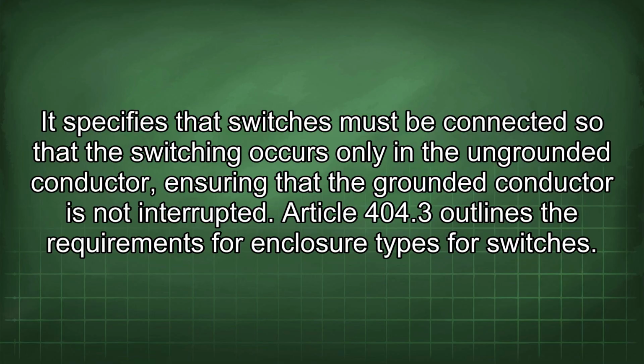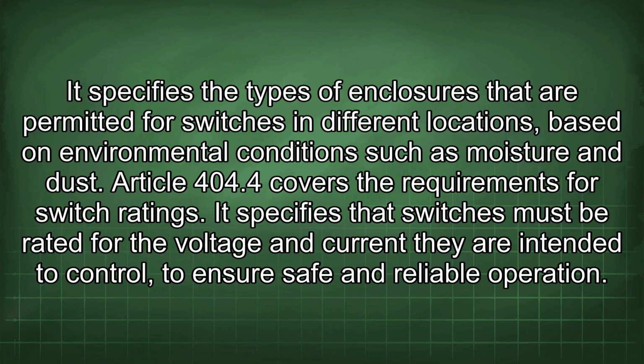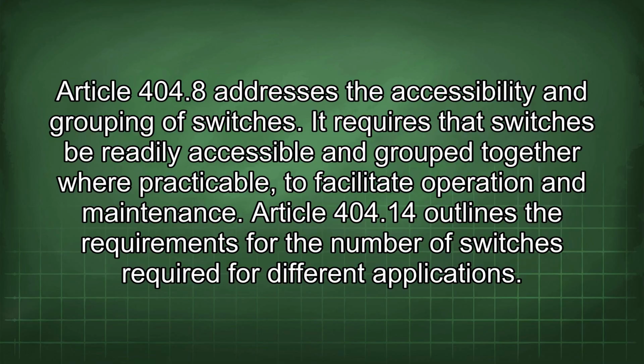Article 404.3 outlines the requirements for enclosure types for switches. It specifies the types of enclosures that are permitted for switches in different locations based on environmental conditions such as moisture and dust. Article 404.4 covers the requirements for switch ratings. It specifies that switches must be rated for the voltage and current they are intended to control to ensure safe and reliable operation. Article 404.8 addresses the accessibility and grouping of switches. It requires that switches be readily accessible and grouped together where practicable to facilitate operation and maintenance.